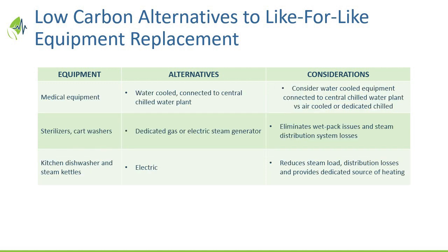So a final little piece here: even medical equipment. If medical equipment is being spec'd and it's got an air-cooled condenser attached to it, you're sentencing yourself to rejecting that heat through the winter forever. It needs to be water-cooled. Whoever's making that decision, you've got to be there, because when it's water-cooled you can connect it up to the chilled water system.